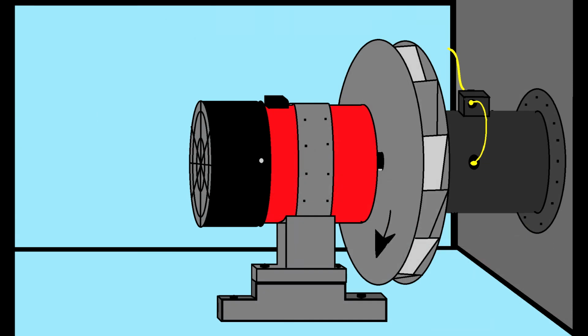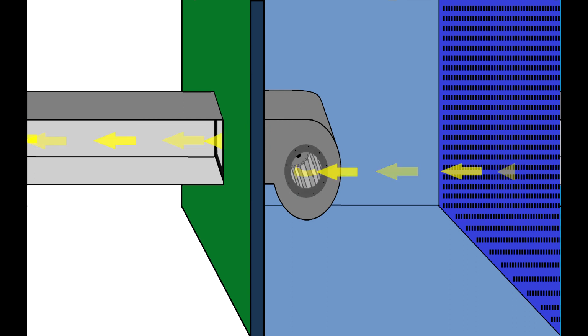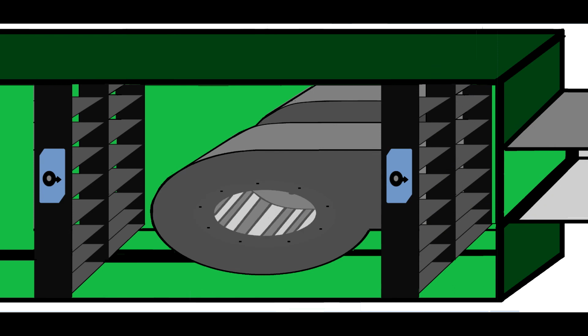Like I said, pros and cons. This fan is inside the chamber and generates heat, which will create a little bit of strain on the cooling coil. Like the other fan, you can use this type of scroll fan, which has the motor inside. They also generate heat, but again, you have full electrical and mechanical redundancy. You don't have belts, they're individual. You run them in pairs, and if one of them gets broken, in this case, there's not too much you can do, and I will show you what you should do to design a good system.